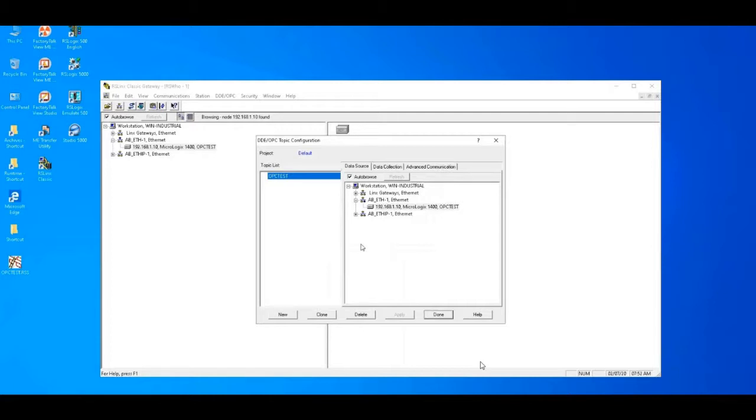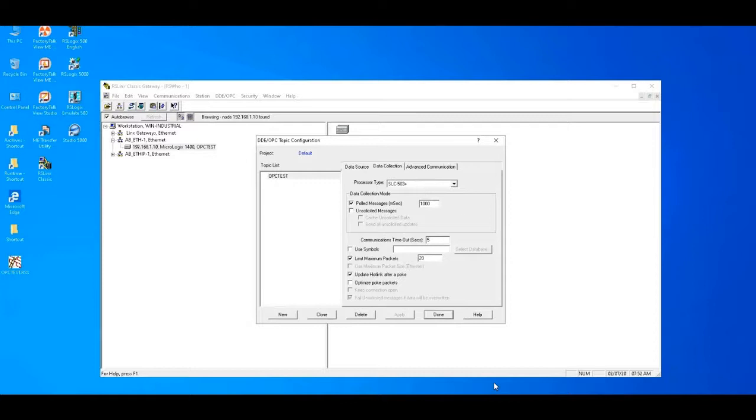After this, we highlight this OPC Test channel name and select the controller on the right side, 192.168.1.10. By default for Micrologix, we can leave this SLC 503+ selection. If your controller is a CompactLogix, we can select Logix 5000. The poll message cycle time we leave at 1000.